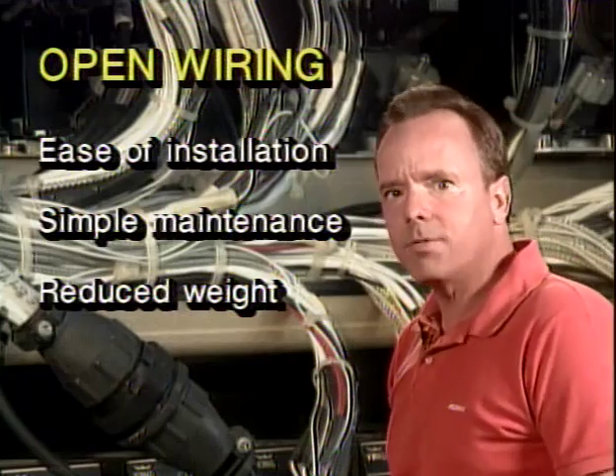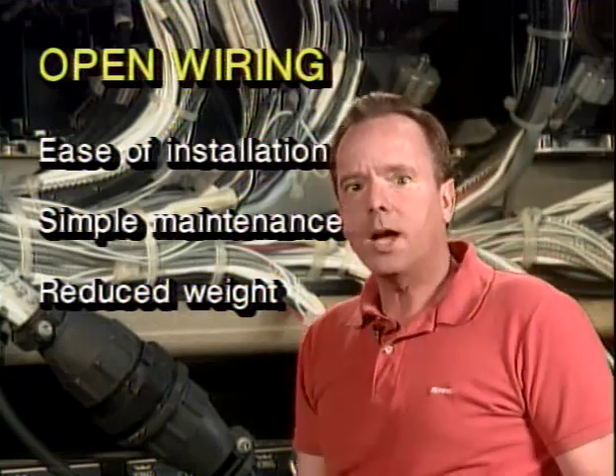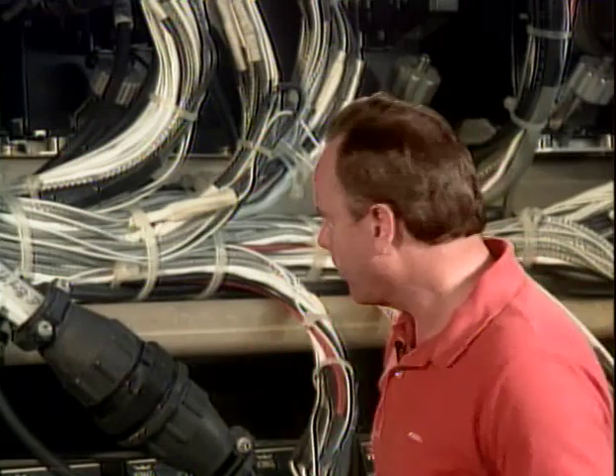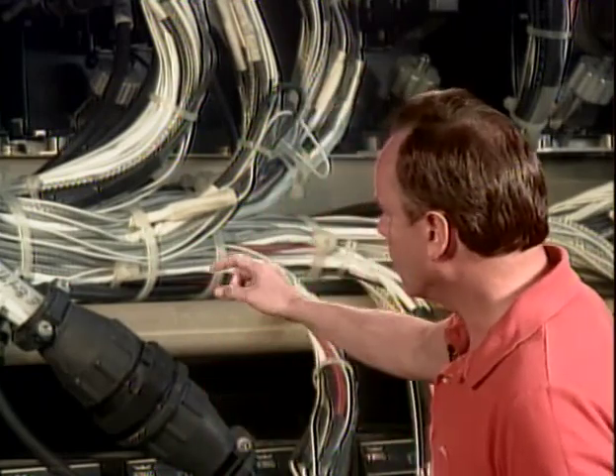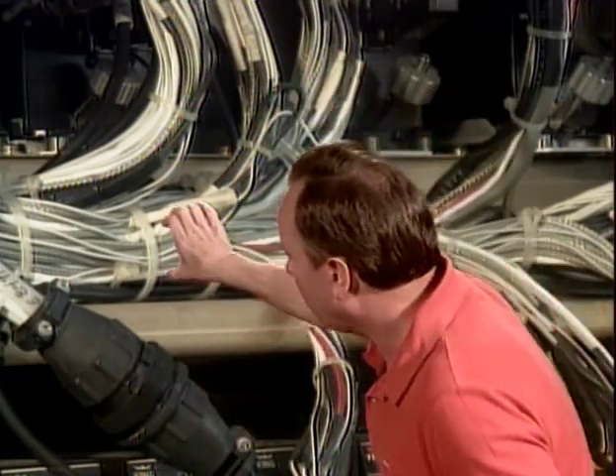So those are the advantages of open wiring. Now you can bundle open wiring together, obviously, as is done here. But the bundle should be limited as to the number of cables, the FAA wants you to know, and the reason for that is to minimize damage from a single electrical fault. What they're saying is you can get a short here, and if the wire gets very hot, you can ruin every wire in the entire bundle. So you need to think about that and limit the number of cables that you put in a bundle.